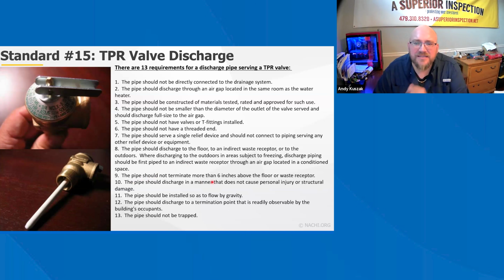The pipe should not terminate more than 6 inches above the floor or the waste receptor. That is for if the temperature pressure relief valve pops off, you're looking at, what did we say, 210 degrees and 150 psi. Your house water should be anywhere from 60 to 80 psi. So if you're looking at 150 psi and 210 degrees, you're looking at steam and extremely hot water.